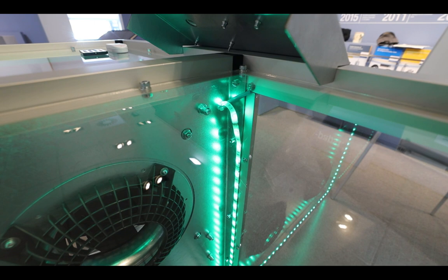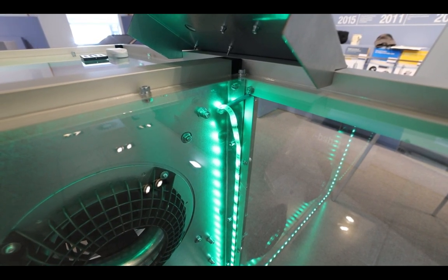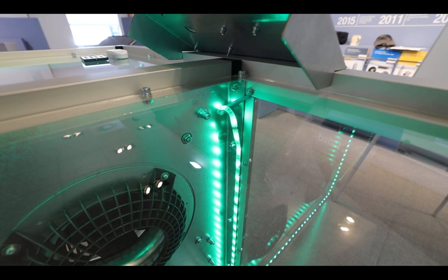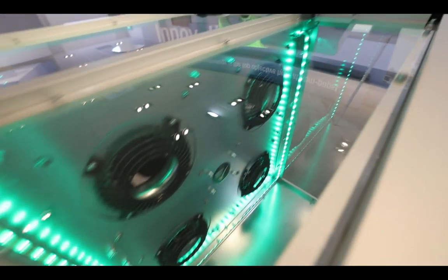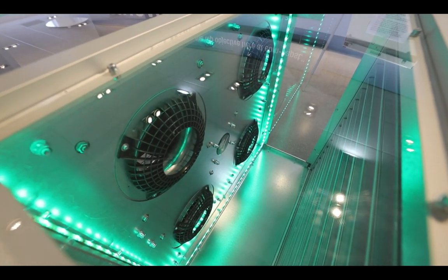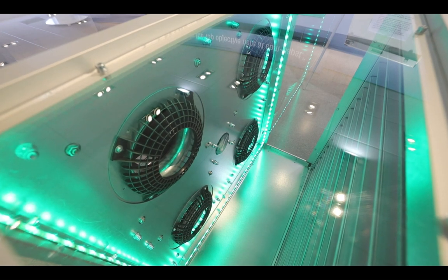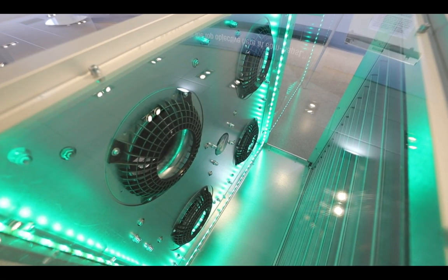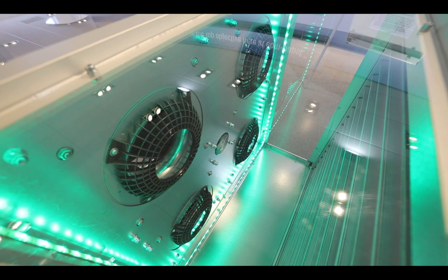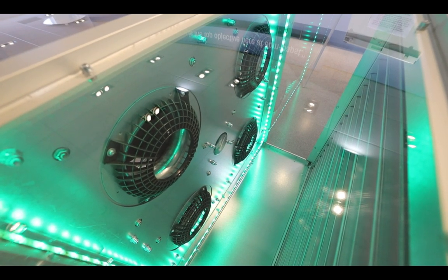In a corner of the suction side plenum, we've installed a pressure tapping in a still non-turbulent area to measure static pressure. The fan array, complete with flow grids, is installed in a mounting plate separating the intake and exhaust plenums. On the demonstration units we'll be using, there'll be a 2-fan and a 4-fan version that will show the various options for volume flow or pressure measurement.